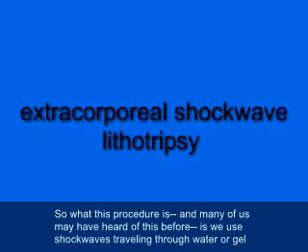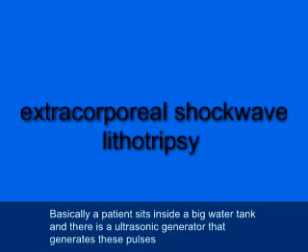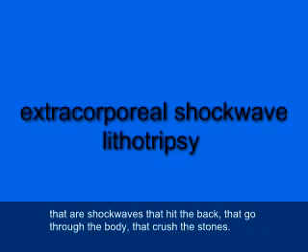So what this procedure is, and many of us may have heard of this before, is we use shock waves traveling through water or gel that will then crush the stones inside the body without the need for surgery. Basically, the patient sits inside a big water tank, and there's an ultrasonic generator that generates these pulses that are shock waves. They hit the back, they go through the body, they crush the stones.